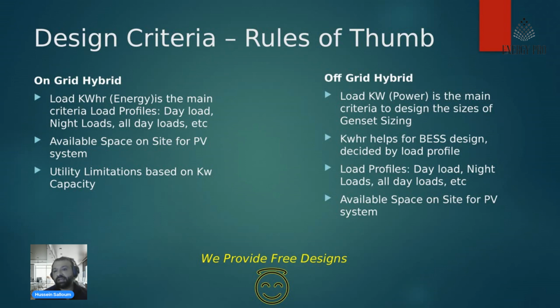And then you have to see, in case you need to put in a battery system, how many hours you need to use that load and what the profile is. Is it a night load, a day load, or a different percentage of the load coming in the day and a different percentage going in the night? Based on that, you design your battery backup system. And finally, your PV system comes in line with the space available. As we said, normally we design for 60% of the maximum load, but in case there is no space available, then you have to reduce it based on the available space. So as we've seen before, for a 1 megawatt system, we put in 600 kilowatt of PV. But in case there's no space for more than 300 kilowatt, then we have to put in 300 kilowatt and design accordingly.